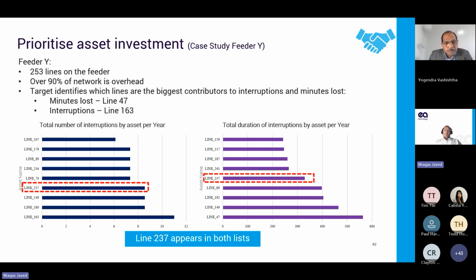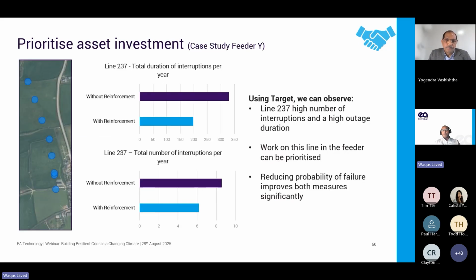This is the kind of insight that often gets missed in average feeder-level assessments. With this level of granularity, we were able to recommend line 237 as a priority candidate for targeted investment, where refurbishment, automation, or structural reinforcement will help to reduce the outages. By applying this asset-specific lens across the whole feeder, the DNO could create a ranked list of critical interventions, enabling a data-driven, optimized resilience investment plan, fully aligned with customer impact and regulator expectations.